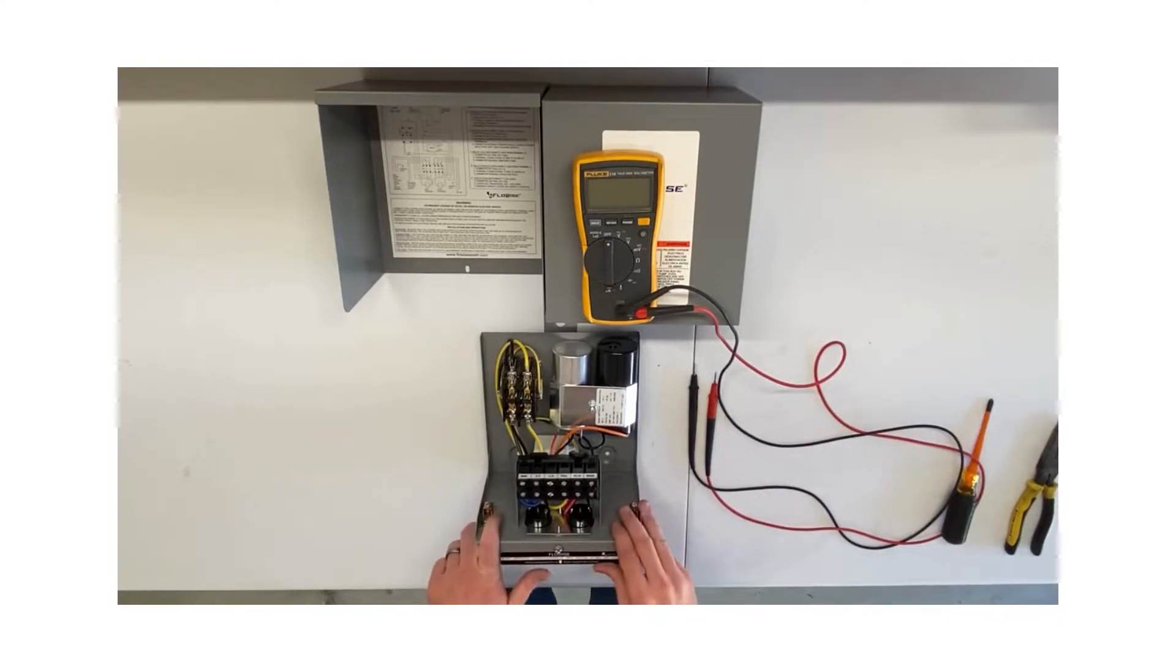I have in front of me a three horsepower single phase 230 volt deluxe box. I'm going to be using the deluxe box for this example because it has all the same components as a standard box and a QD box, plus an additional contactor. The procedure and readings will be the same no matter which box you have.